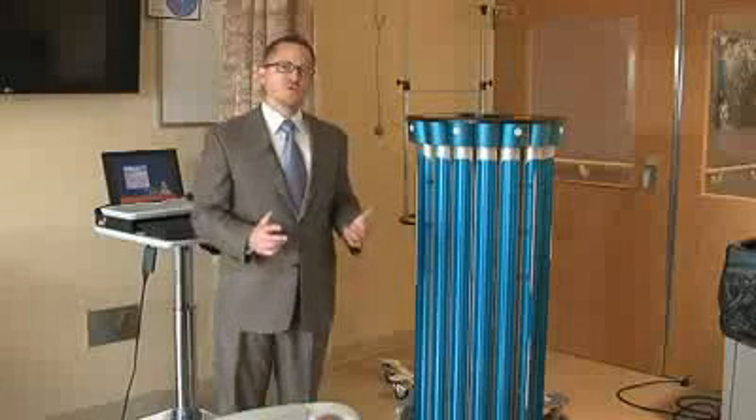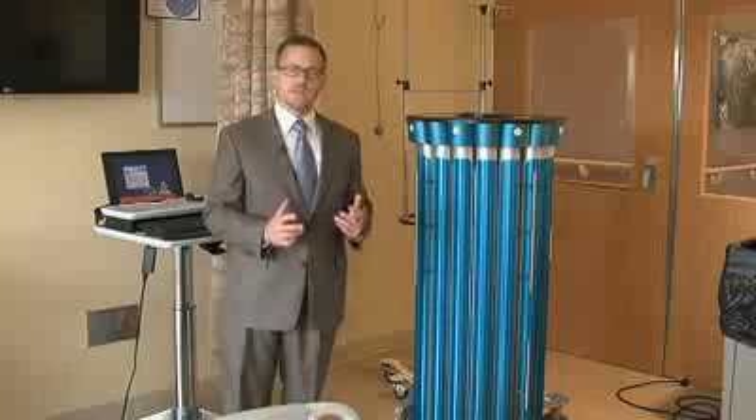It's been very difficult to determine the endpoint dose. With our sensing technology and advanced algorithm, the device generates a very high-intensity UVC field in the room, balances that field, properly manages the power available, and measures the UV field until we reach a desired endpoint dose. When that dose is reached, the device turns off and the room is treated.